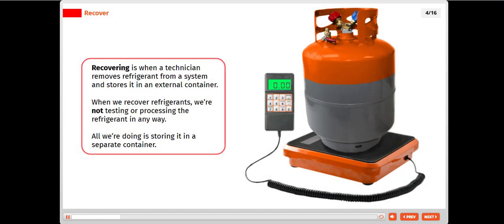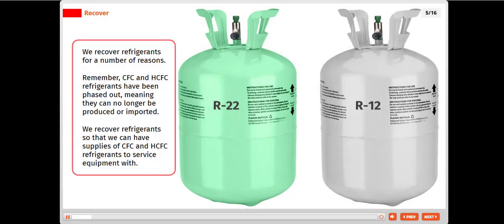Recovering is when a technician removes refrigerant from a system and stores it in an external container. When we recover refrigerants, we're not testing or processing the refrigerant in any way. All we're doing is storing it in a separate container. We recover refrigerants for a number of reasons. Remember, CFC and HCFC refrigerants have been phased out, meaning they can no longer be produced or imported. We recover refrigerants so that we can have supplies of CFC and HCFC refrigerants to service equipment with.